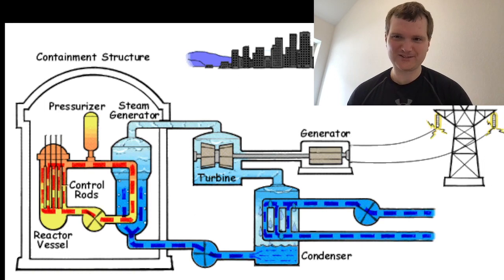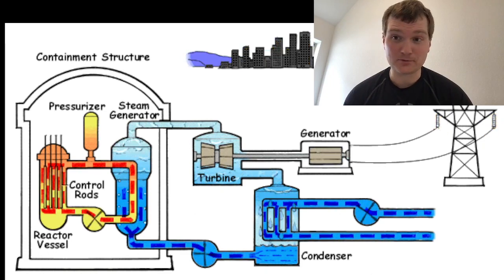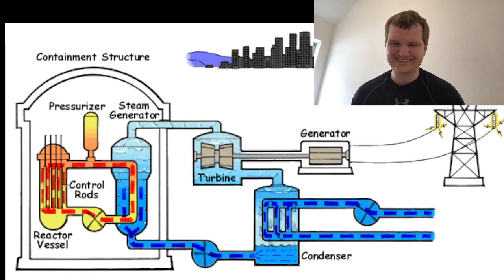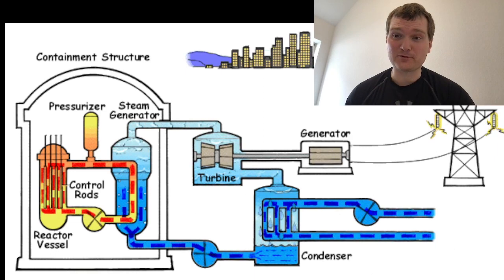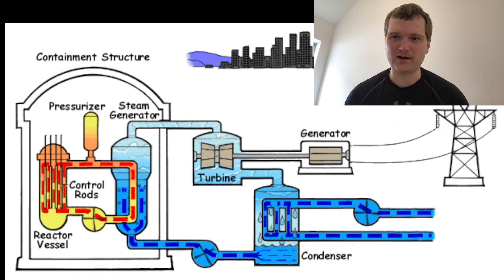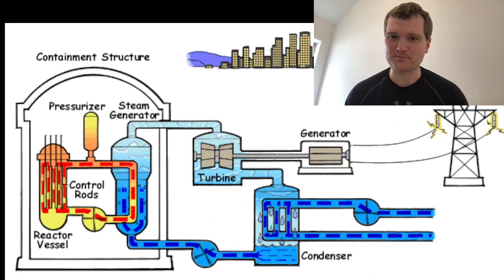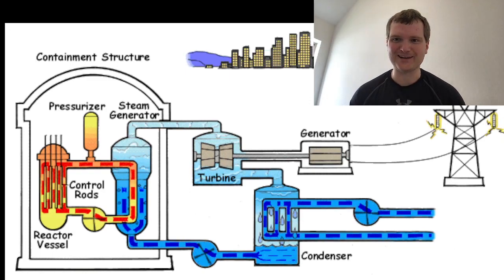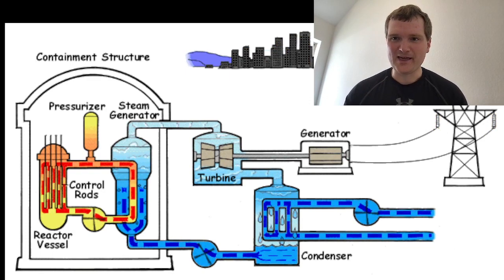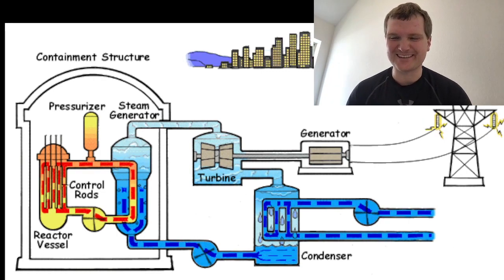But there's one major thing he left out as far as a pressurized water reactor: the pressurizer. Yes, everything that's done in the reactor vessel is at very high pressure on the order of 2200 PSIG plus. So that water, it's water, but it's very hot water on the order of over 500, 600 degrees Fahrenheit. So yeah, the pressurizer is a very important piece of the pressurized water reactor that he left out.